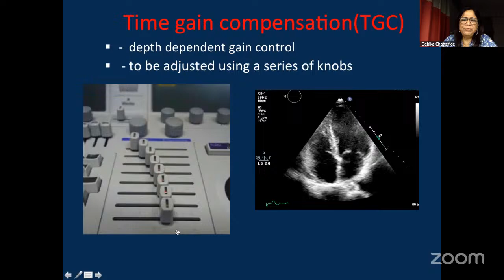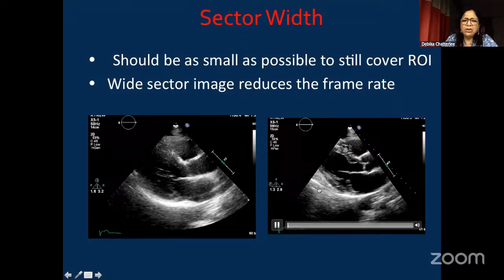And the sector width of the image should not be very big. It should be as small as possible, yet cover the region of interest, because a wider scan reduces the frame rate. Your image quality will be compromised. Look at these two images. You can really appreciate the clarity of this image where the width is optimum.